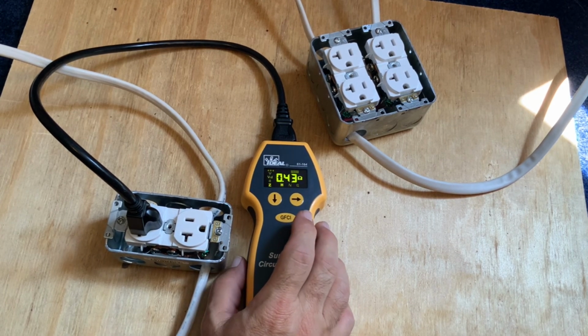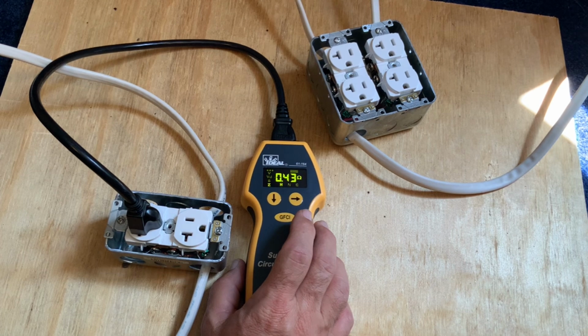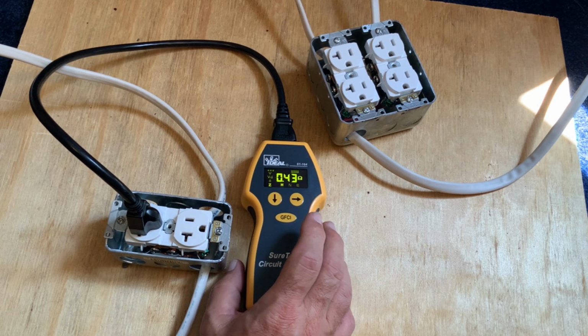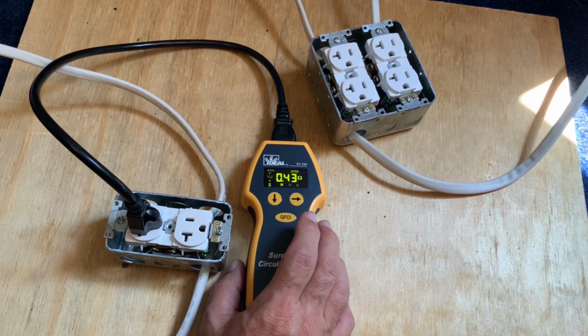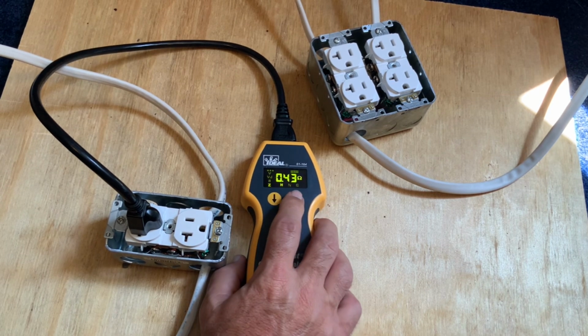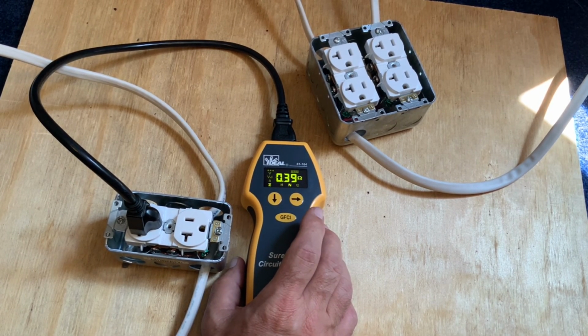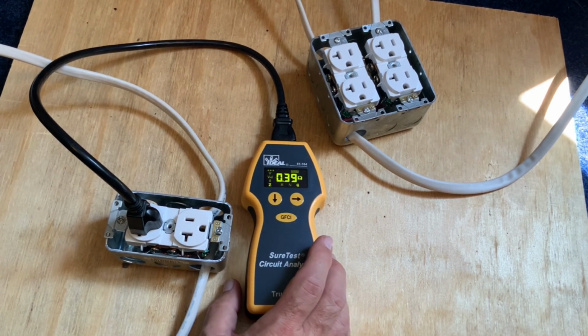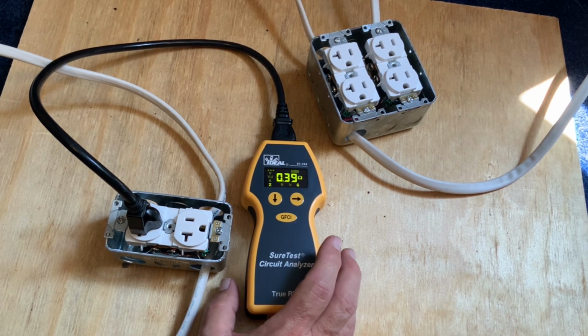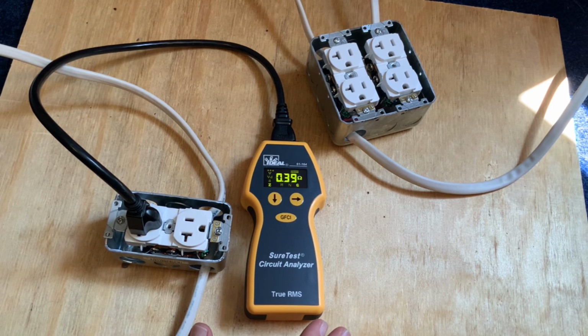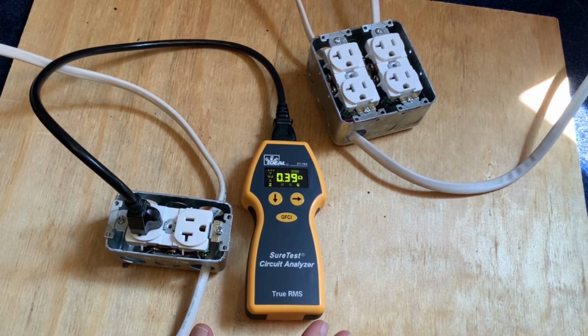The impedance function of this tester measures the actual resistance of the wire. Since this is a dedicated wire, I know the resistance. I actually measured it out at 0.38 ohms with a 4-wire ohm meter. So right now I'm showing 0.43 ohms on my hot. That's because that also includes the resistance of the breaker. But if I look at my neutral, I'm measuring 0.39 ohms. So this is pretty accurate compared to the 0.38 that I measured with my 4-wire meter, and 0.39 ohms on the ground wire, which I would expect because this is a controlled environment with the ground and neutral being exactly the same length in my test setup here. So very accurate on measuring impedance.